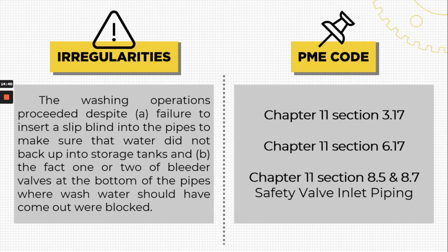Sections 3.17, 6.17, 8.5, and 8.7 state that in order to operate satisfactorily, a safety valve must be mounted vertically. It should be directly on the vessel nozzle or on a short connection fitting that provides direct and unobstructed flow between the vessel and the valve. Safety valves protecting pipe systems should of course be mounted in a similar manner. The device may never be installed on a fitting having a smaller inside diameter than the safety valve inlet connection.